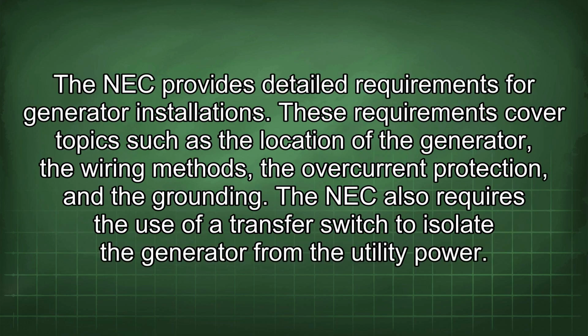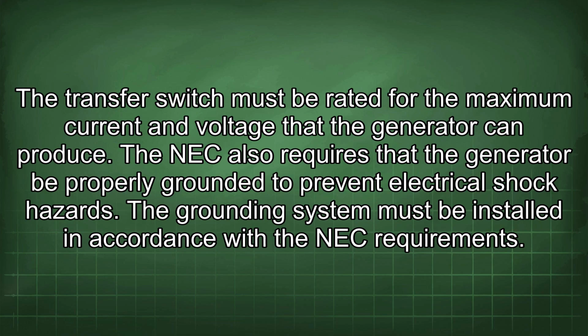The NEC provides detailed requirements for generator installations. These requirements cover topics such as the location of the generator, the wiring methods, the overcurrent protection, and the grounding. The NEC also requires the use of a transfer switch to isolate the generator from the utility power. The transfer switch must be rated for the maximum current and voltage that the generator can produce. The NEC also requires that the generator be properly grounded to prevent electrical shock hazards. The grounding system must be installed in accordance with the NEC requirements.